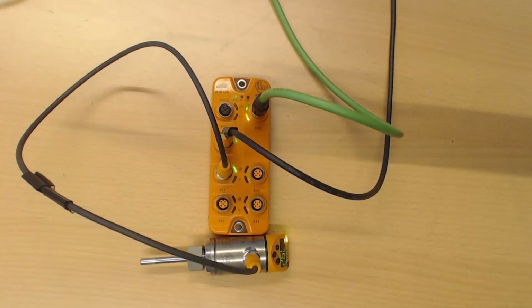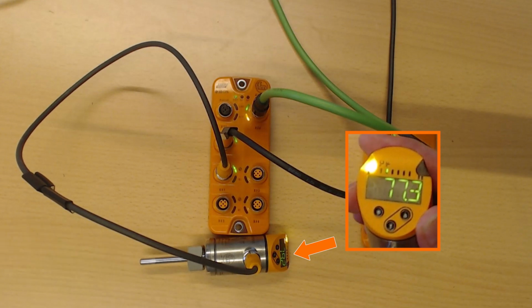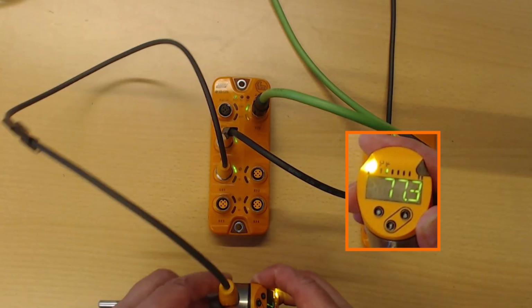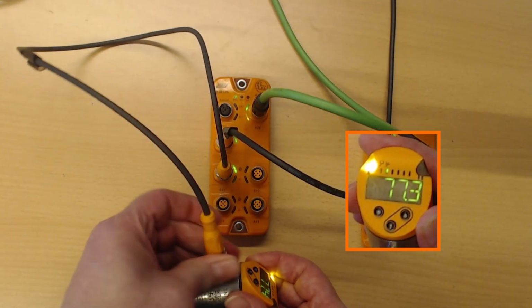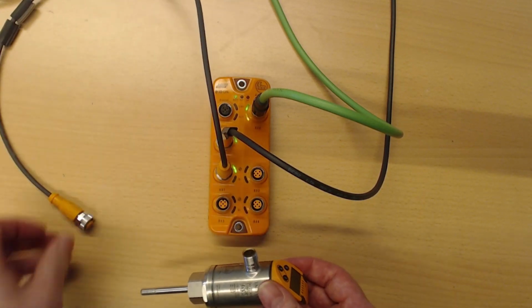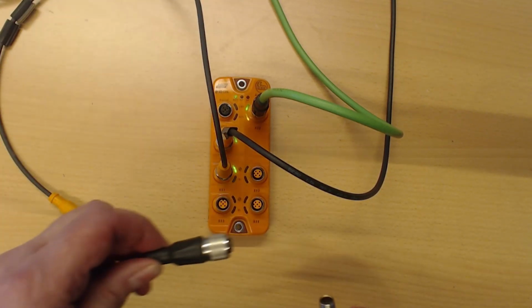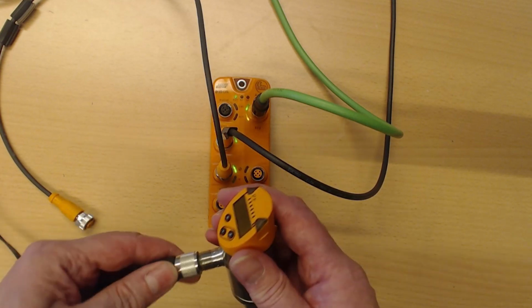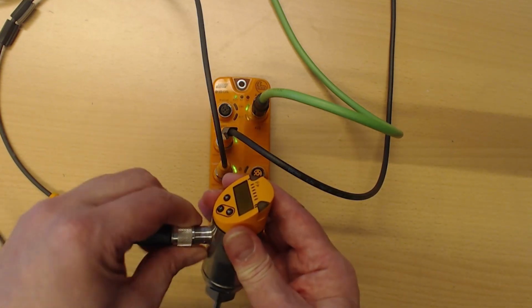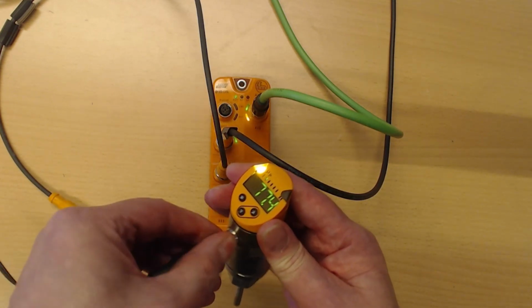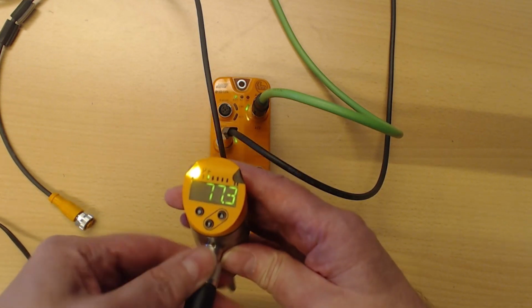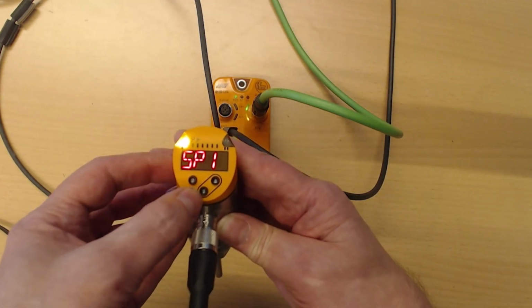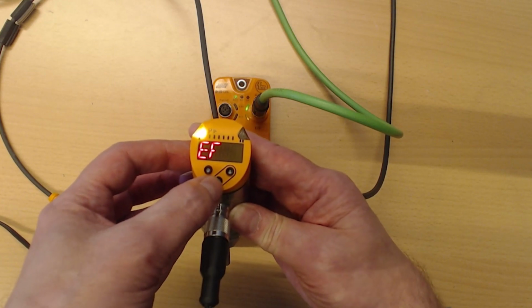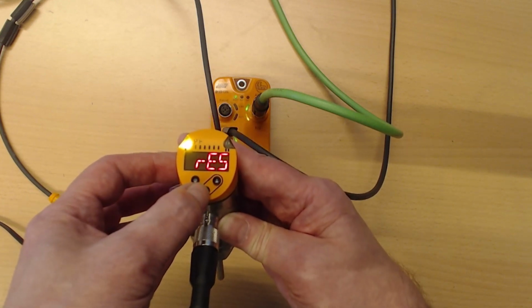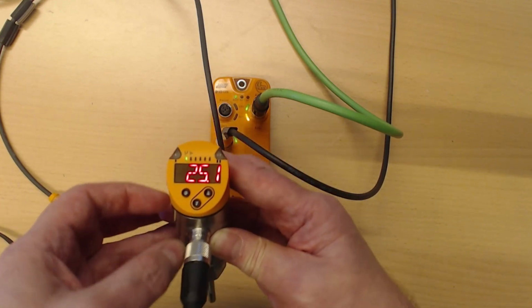Let's now move on to the parameter storage function. As we can see, the current temperature value is displayed in green with the unit degrees Fahrenheit. This parameter is set with a green display, and the unit degrees Fahrenheit is stored in the IO link master due to the backup and restore function. We disconnect the sensor and connect it to a separate power supply without connection to the master or controller. To restore the factory settings, we use the push buttons on the device. As we can see, the sensor display is red by default, and the unit is degrees Celsius.